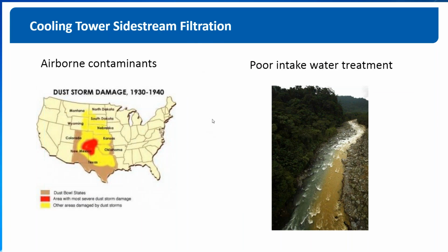Now I'm going to talk about cooling tower sidestream filtration. Now, the two factors you need to consider when selecting or considering a sidestream filter are the airborne contaminants. In the States, there are significant areas with dust contamination, but other things to consider are pollen and basically any other airborne contaminants. And then also when there is poor intake water at the site, sidestream filtration can be used as a very good remedy to keep the water in the cooling tower clean.